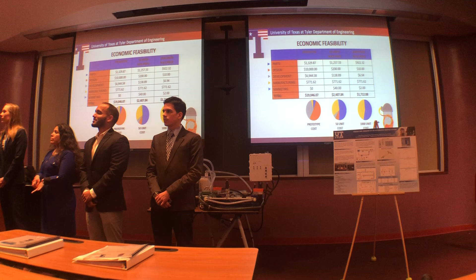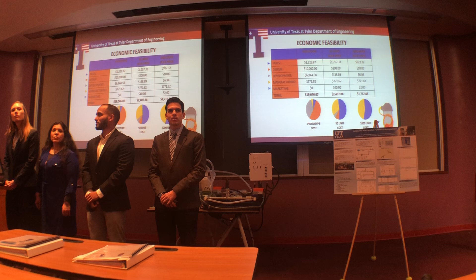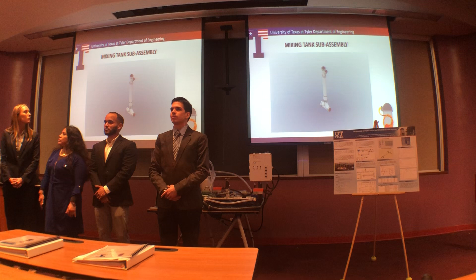How do you notify the user of an alarm condition? I'm sorry, what was that? How do you notify the user of an alarm condition? So essentially, on the LabVIEW software, the interface has a no-flow alarm indicator. At the bottom left, you see no-flow alarm. That indicator will turn on and then pretty much kill power to the whole system. There is a solid-state relay inside that control panel, and that solid-state relay feeds all our breakers and everything, so we can cut power to the whole system.